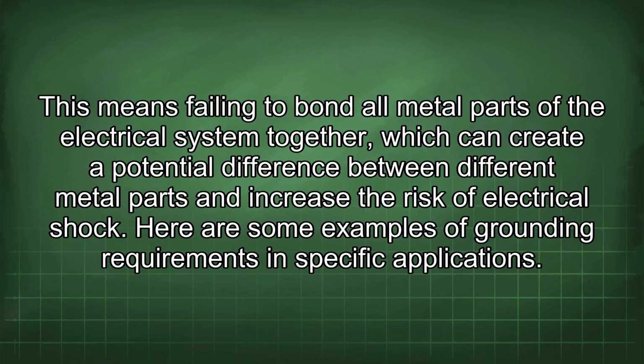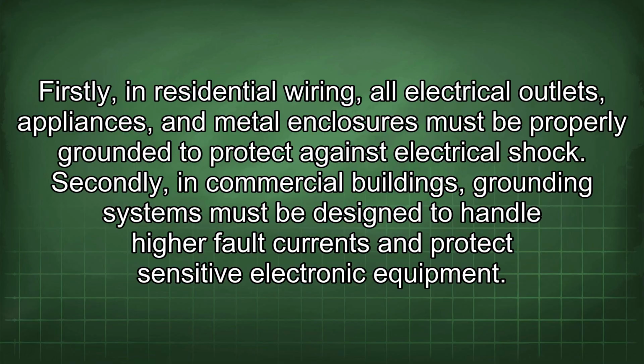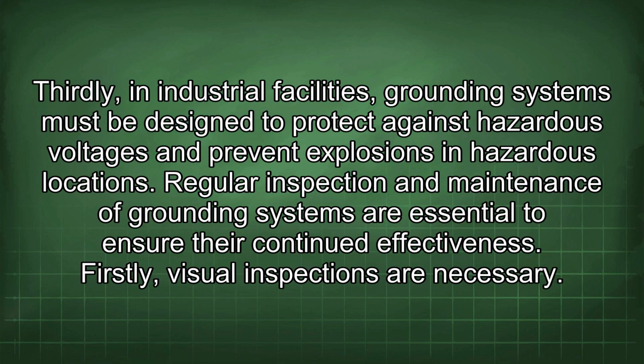Here are some examples of grounding requirements in specific applications. Firstly, in residential wiring, all electrical outlets, appliances, and metal enclosures must be properly grounded to protect against electrical shock. Secondly, in commercial buildings, grounding systems must be designed to handle higher fault currents and protect sensitive electronic equipment. Thirdly, in industrial facilities, grounding systems must be designed to protect against hazardous voltages and prevent explosions in hazardous locations.